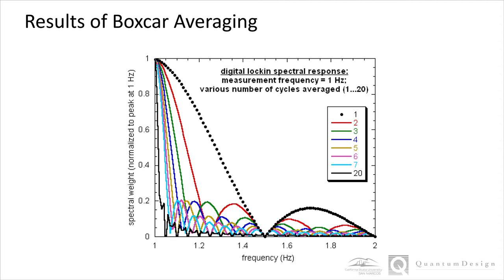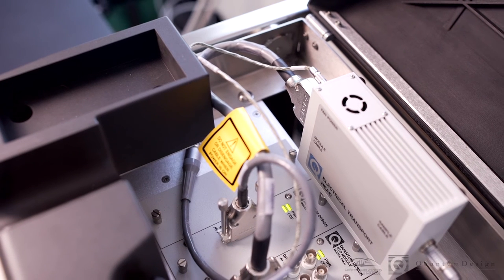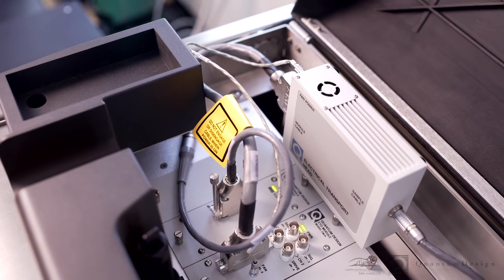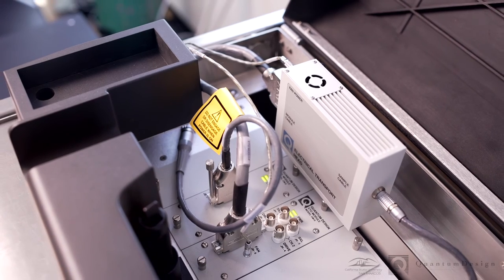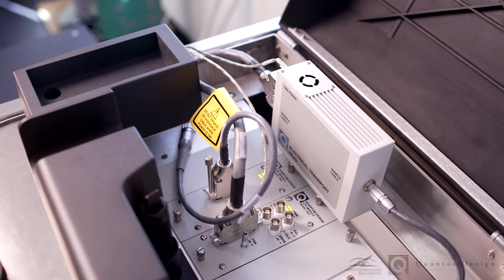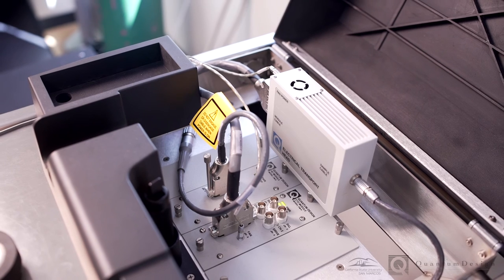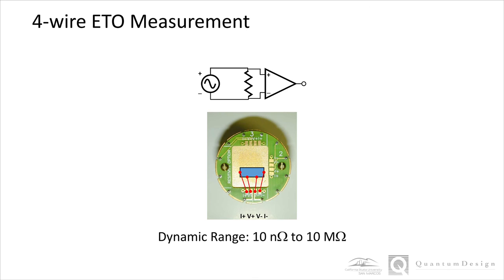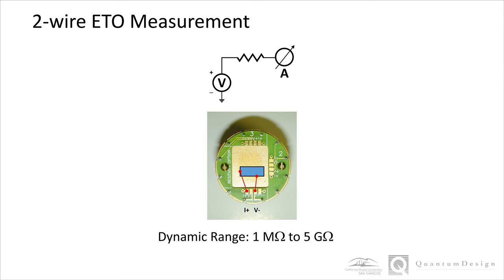The ETO possesses two measurement channels with their own dedicated electronics, meaning that two sets of precision current sources and voltmeters are individually running at all times. The current source's maximum output is 100 milliamps with 1 nanoamp minimum precision. And the output modes include DC or AC, with a frequency range between 0.1 Hz to 200 Hz. The ETO can operate in a low-impedance 4-wire measurement mode or a high-impedance 2-wire measurement mode. In the 4-wire mode, the acceptable impedance range is between 10 nano-ohm and 10 mega-ohm. Two-wire measurements can be performed from 1 mega-ohm up to 5 giga-ohms.